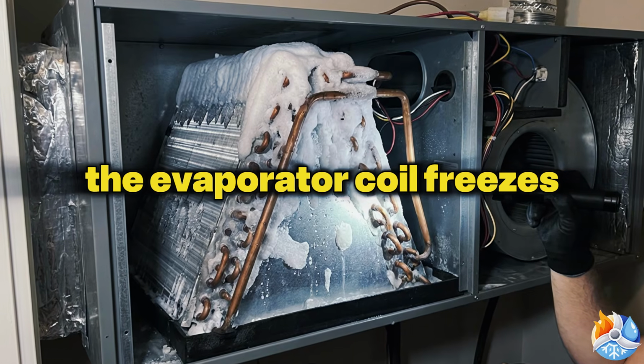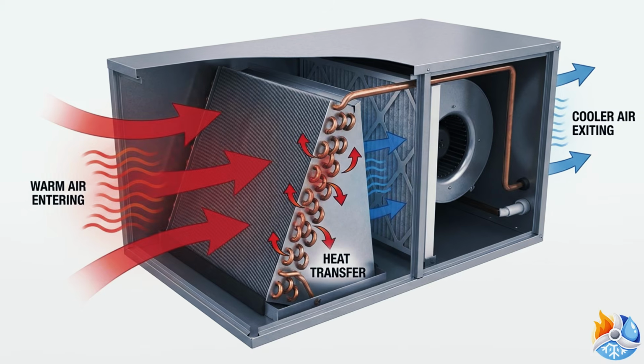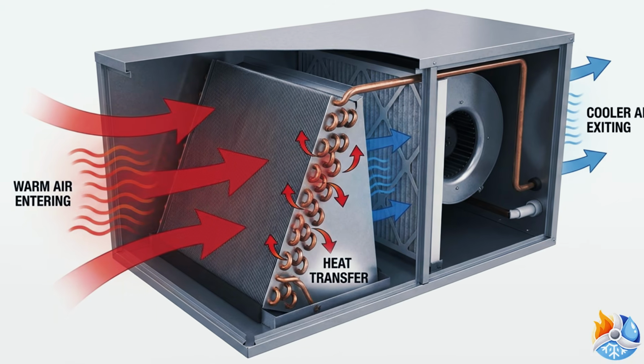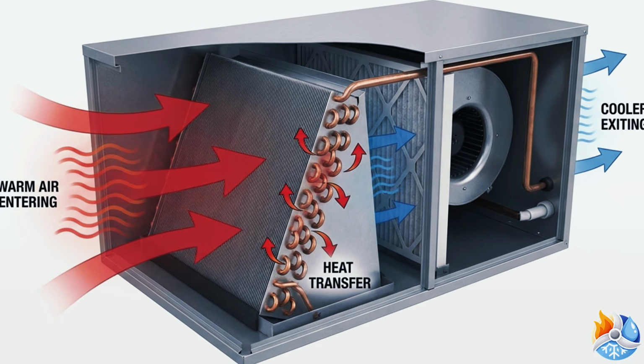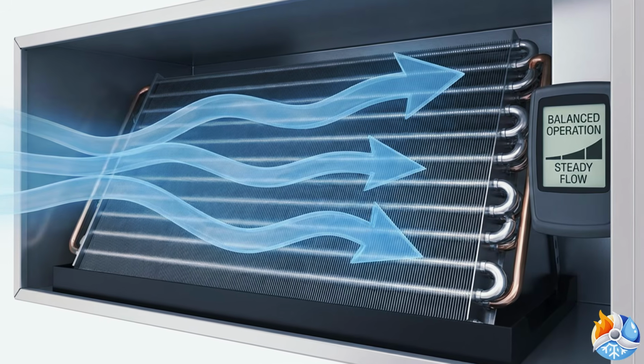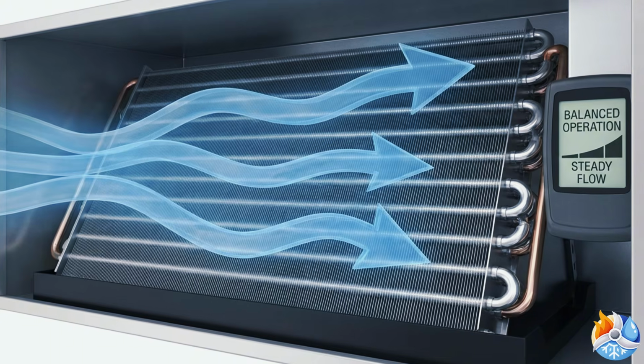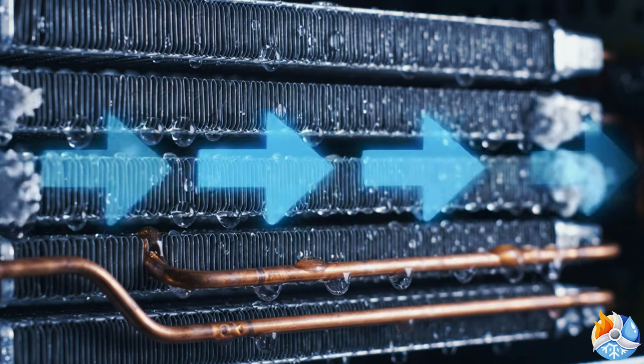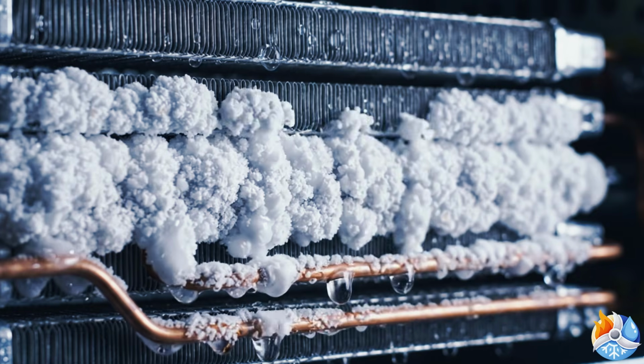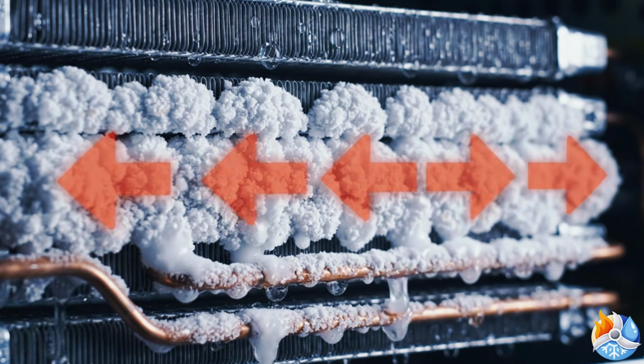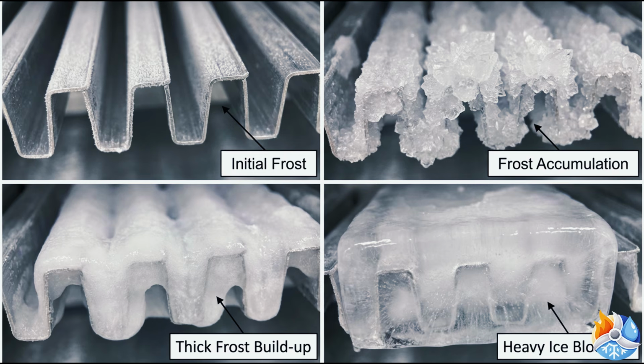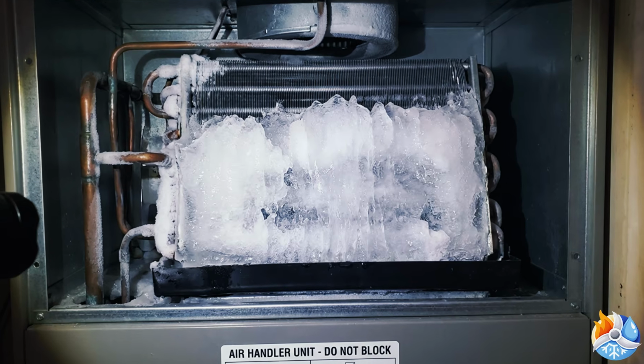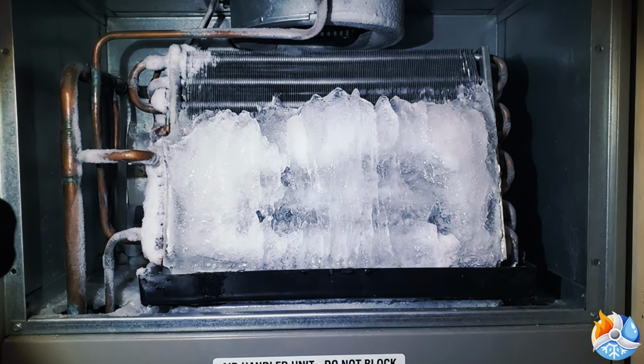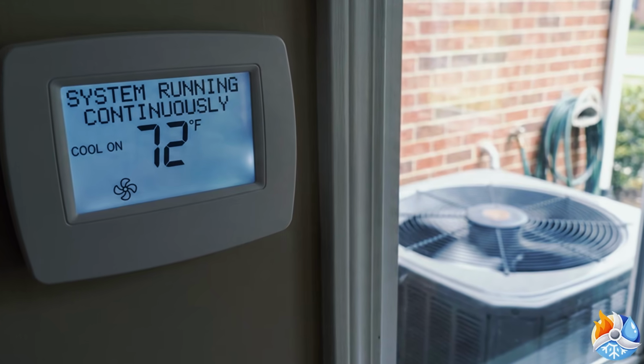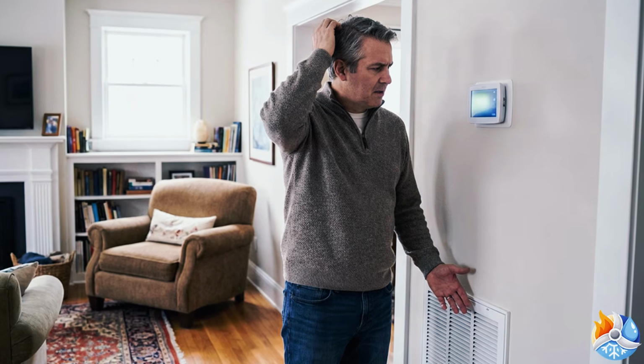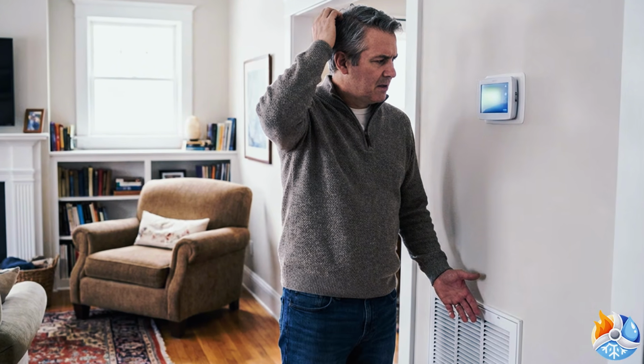First, the evaporator coil freezes. Your evaporator coil is the part inside the air handler that gets cold and pulls heat out of your air. For that to work, warm air has to flow across it continuously. Restrict that airflow, the coil gets too cold. Moisture in the air freezes right onto it. Ice forms. More ice forms. Soon, you have got a solid block of ice where your coil should be. The system runs non-stop. The house does not cool. And the homeowner has no idea why.